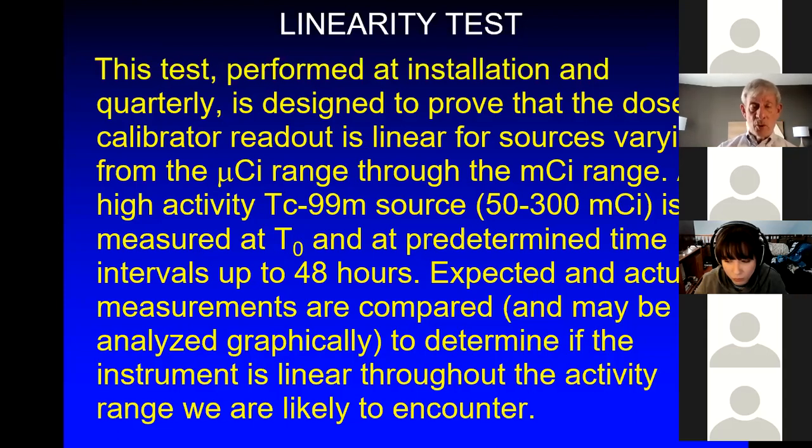There's also another way to do this, by the way, called the Lineator, made by Calicheck. There are some lead sleeves that fit within each other, and you can do this whole test in 10 minutes instead of in 3 days. But let's say we're doing the 3-day test.